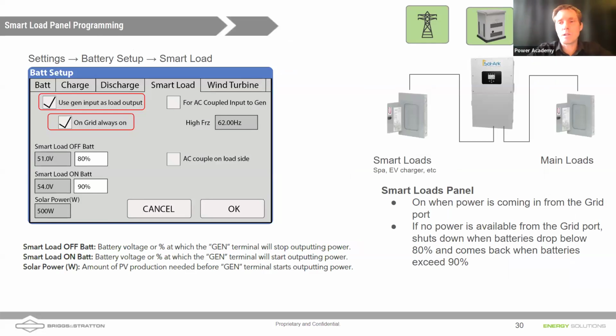So what we can do here by putting those loads on a smart load output panel, we've got 80 amps of continuous power that could pass through to that panel. That's the 19 kilowatts of pass through on the gen port. But what we do is we come into the battery setup and we would go to smart load. And under the smart load tab, we could tell the inverter, use the generator input as a load output by checking this box. And as long as the grid is present, we could always keep those loads powered. So we check this box that says on grid, always on.